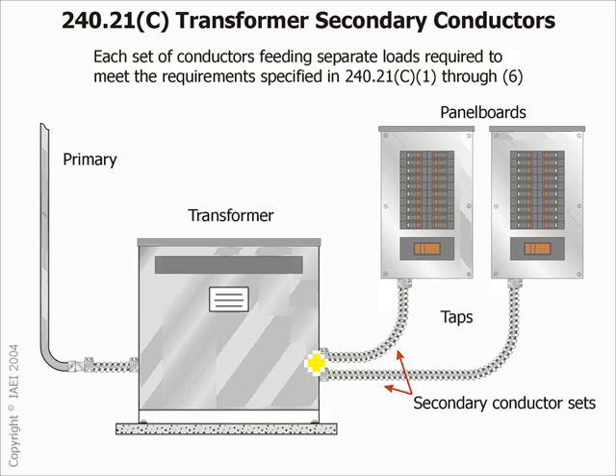What are the rules though? Anybody remember the rules? So let's suppose that this was 100 amp. Let's take 100 amp here. This is 100 amp, and this was 200 amp. So what do you guys think the conductors here have to be minimum? Anybody? No, this set. Is the color okay? 100 amp. So what do you think this conductor set minimum has to be? 200 amp. They can't be less than 200 amp, the load at the end of it.